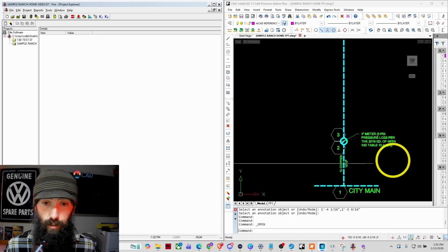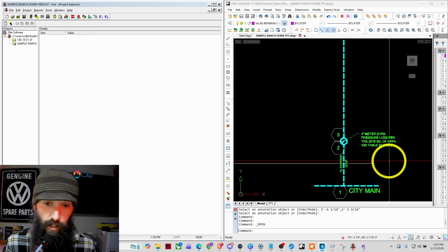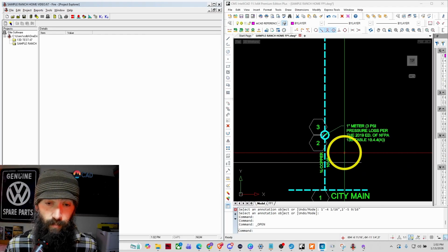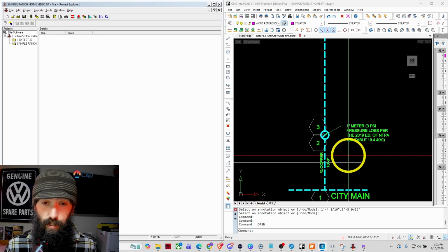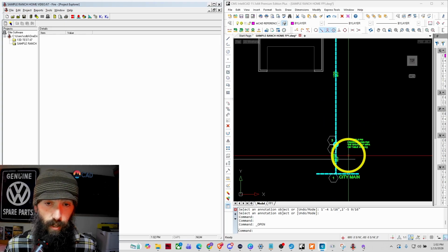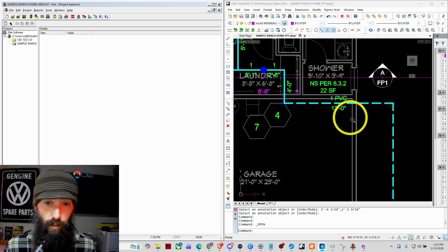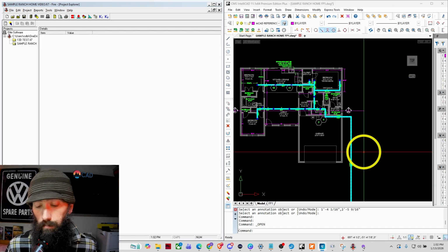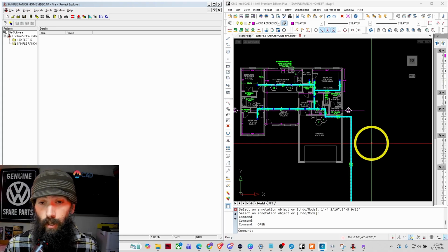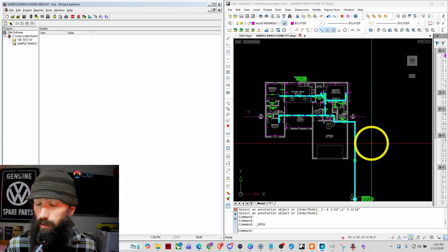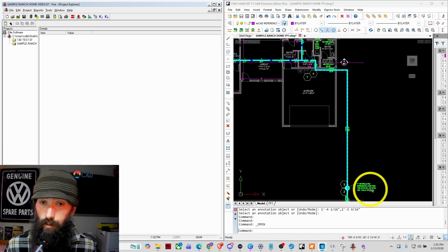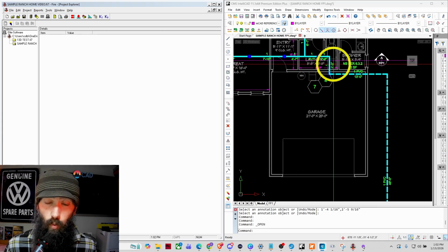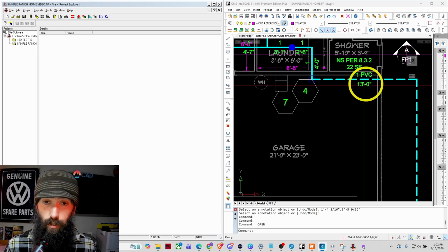We just put a common underground for our area anyway. A lot of times they'll have 10 feet from the city main to the meter out of 3/4 inch copper, and then it will go from there to the house in 1-inch PVC or maybe 1.25 PEX, 1.5 PEX, that type of thing. They might want to do 1-inch PEX, but that usually will not work with the sprinkler system. 1-inch PEX is a much smaller internal diameter.